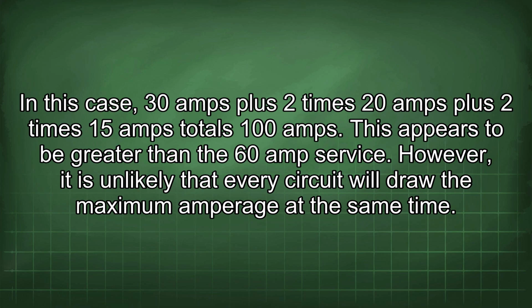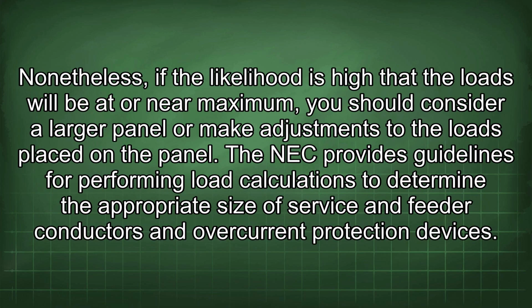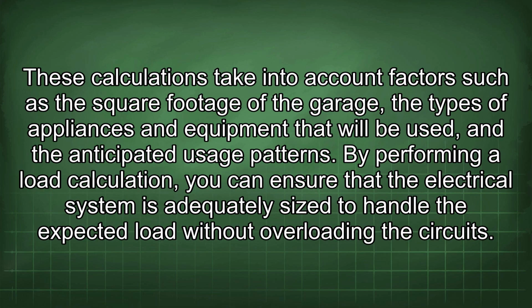However, it is unlikely that every circuit will draw the maximum amperage at the same time. Nonetheless, if the likelihood is high that the loads will be at or near maximum, you should consider a larger panel or make adjustments to the loads placed on the panel. The NEC provides guidelines for performing load calculations to determine the appropriate size of service and feeder conductors and overcurrent protection devices. These calculations take into account factors such as the square footage of the garage, the types of appliances and equipment that will be used, and the anticipated usage patterns.